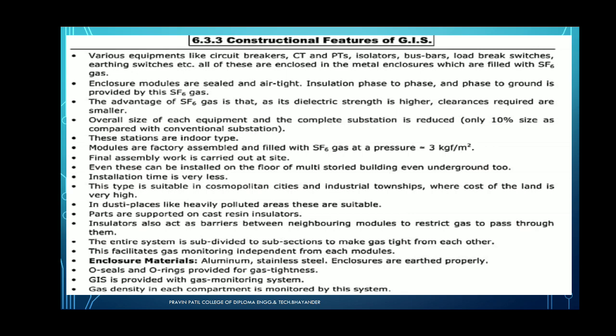Enclosure materials such as aluminum, stainless steel enclosures are earthed properly. O-seals and O-rings provide the gas tightness. The gas insulated substation is provided with gas monitoring systems. Gas density in each compartment is monitored by these systems. So these are the main features of the gas insulated substation which is used in the power systems.